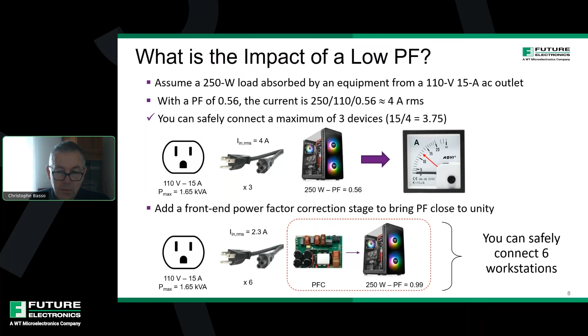Now, if you insert a pre-converter or power factor correction stage for each workstation, they will bring their PF close to unity. The nominal input current now drops to 2.3 amps for each computer, and you can connect up to 6 workstations. The burden on the power cord is also reduced, and you can use a smaller wire gauge for the assembly.